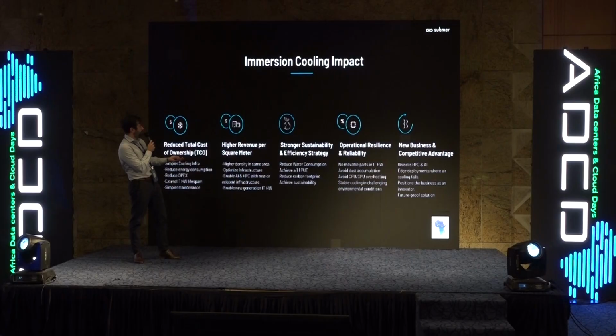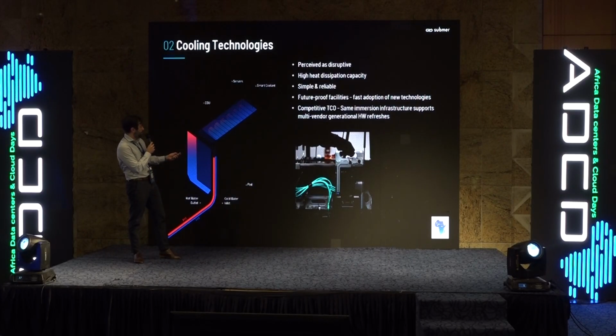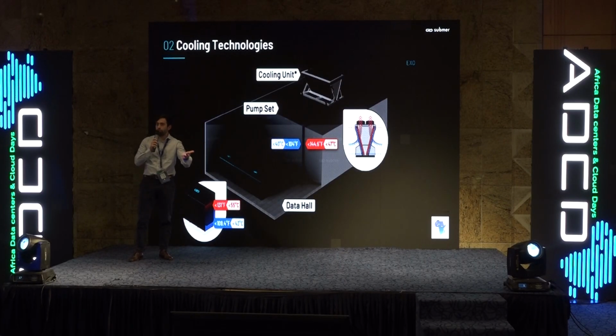Let's go back to this page here. I guess you know what a chiller is, what a dry cooler is. So one important thing here is that you have 40 degrees Celsius - this temperature is basically related to the type of load you have in your tank. The more kilowatts you have in the tank, the colder the water temperature. And then you have the set point - the temperature at which the tank is working. The colder it is, the colder your water temperature. But in general, the water temperatures are going to be higher than 30 degrees Celsius.